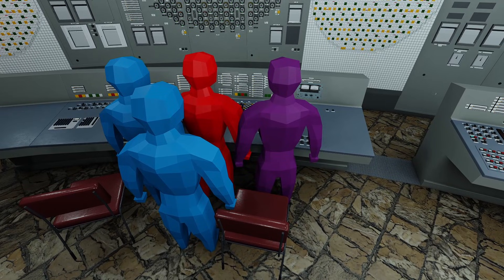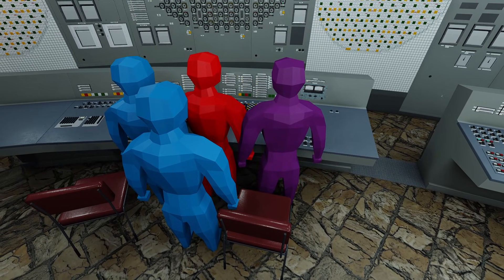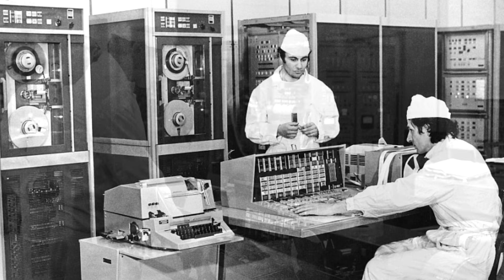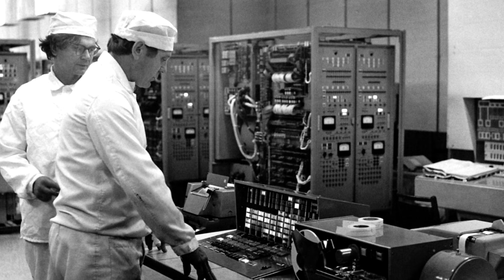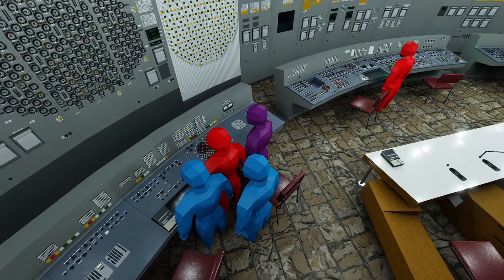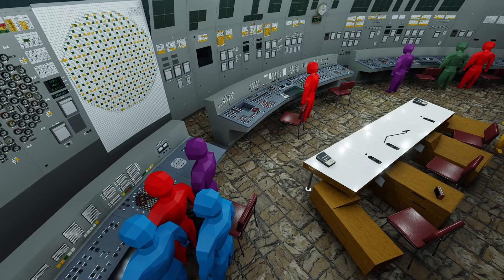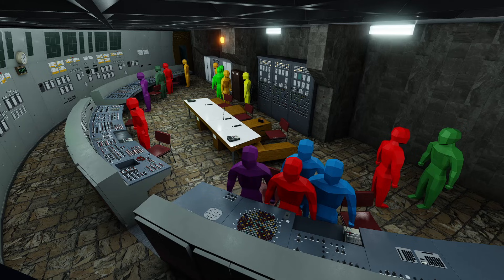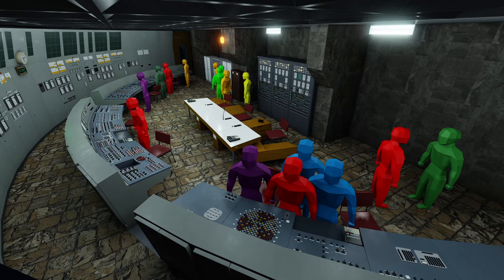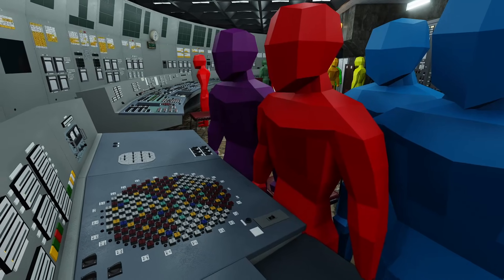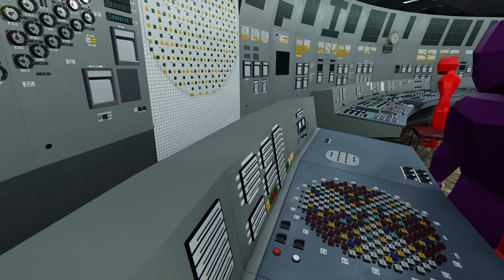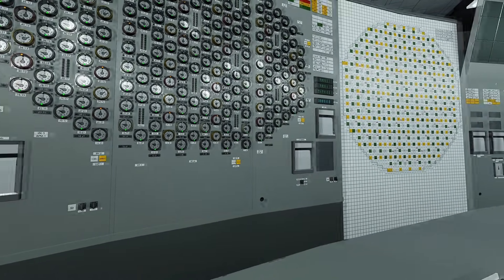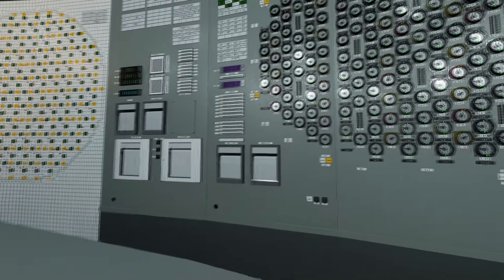But there was more trouble to come for the operators trying to balance all of these issues. In order to prime the computer system, SKALA, to record fresh values from the rundown, the DREG program, which recorded reactor parameters, was turned off and on repeatedly, as new magnetic tape was inserted. With this turned off, the operators are temporarily controlling the reactor blind now in a number of ways. Already they were without the nuclear physics laboratory and its reactor program. Now, for the next 20 minutes, said operators have to contend with being without up-to-date readings from the PRISMA program on the SKALA computer, which provided guidance for the operators on how to operate the reactor. Their devices that calculated the operating reactivity margin would not work because the power was too low. And finally, they didn't know what the new distribution of xenon in the core looked like, which would have changed during the power drop 15 minutes earlier.